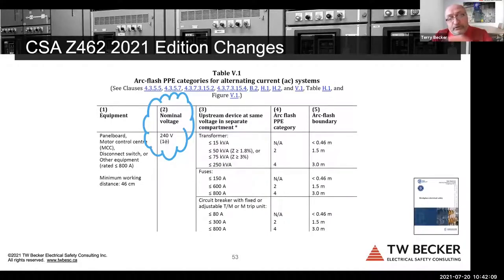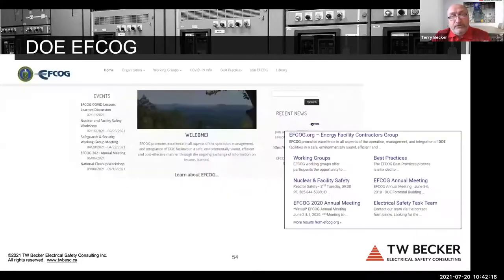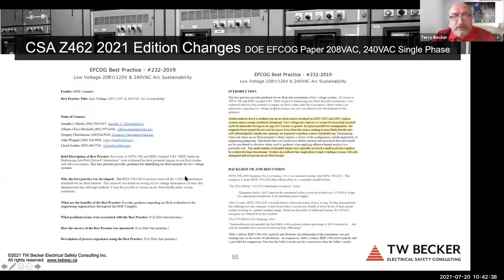I totally disagree with all of this. The other information that's here for 208 volt or higher would be valid, but sustaining an abnormal arcing fault at 240 volt single phase has not been substantiated in 1584. And it may be later, it may be the next phase in 1584's research, which I believe it is based on my involvement. And then what I've got is, this is the DOE in the US, their sort of user group. It's a public website. So they have a publicly available paper that they published where they looked at 240 volt single phase. They say that you can't sustain an abnormal arcing fault at 240 volt single phase.